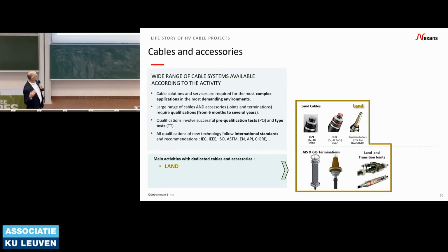Are you working only on a land cable? Then you already have different types of cable possible. Is it AC or DC? Is it aluminum or copper conductor, or copper enameled? Is it even a superconductive cable? Why not? Then it will mostly be medium voltage. And then, of course, you have to be sure you have the adequate certified accessories, and the correct choice in terms of standardization according to what the client requires in his own specification.